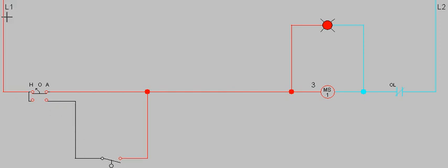So now the current flow comes through. Once we change this, it closes this portion of the selector switch. The top set of contacts are now closed. We have current flow through, activating the pump, and we can put it back in the off state. So there, the switch activated to this side. We have it in hand, which will run the motor, closing this set of contacts. If we put it in automatic, we have to go through and use whatever controls that we have. In this case, it happens to be a float switch.